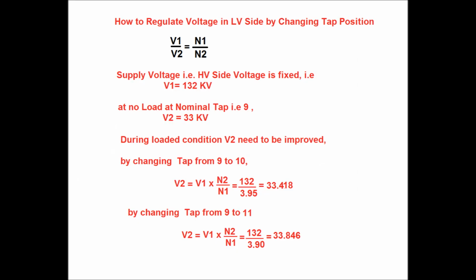Now, how can the LV side voltage be regulated by means of changing the tap position? Since V1 by V2 is equal to N1 by N2, V2 is equal to N2 by N1 into V1, or V1 by turns ratio. So at no load, at a nominal tap position, that is at tap position 9, V2 is 33 kV, and during loaded condition the V2 needs to improve, so that at the distribution end substation the voltage can get up to 33 kV. Since there is more load, there will be a drop in the transmission line, and so the terminal voltage at the distribution end substation drops from 33 kV to almost 31 or 32 kV.